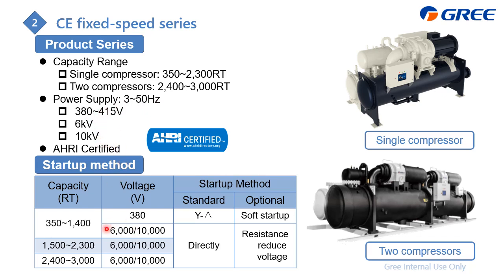And according to different capacity, you can also find different options. The voltage can also be different, and the reason is the start-up method. You can select star-delta or direct start, but for this one you need a higher voltage. And this is the standard, and here is the optional. And all the products have the AHRI certificate.